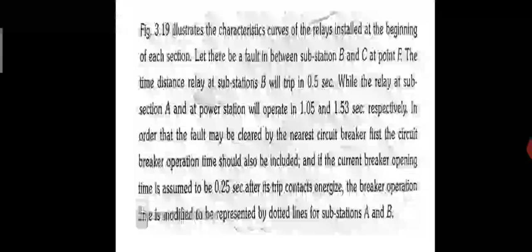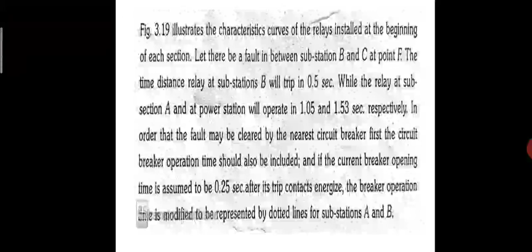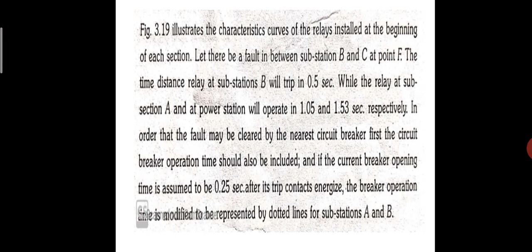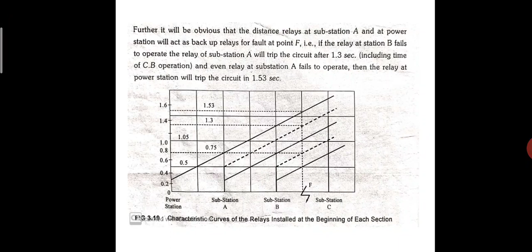The time distance relay at substation B will trip in 0.5 seconds, while the relay at substation A and at power station will operate in 1.05 and 1.53 seconds respectively, in order that the fault may be cleared by the nearest circuit breaker. First, the circuit breaker operation time should also be included, and if the circuit breaker opening time is assumed to be 0.25 seconds after its trip contacts energize, the breaker operation time is modified, represented by dotted lines for substations A and B. Further, it will be obvious that the distance relays at substation A and at power station will act as backup relays for a fault at point F.